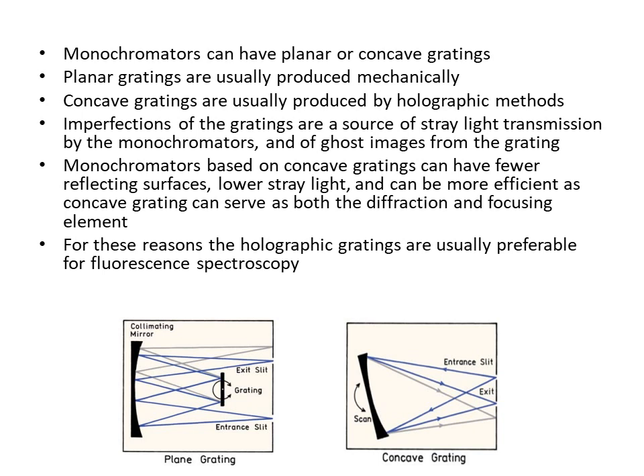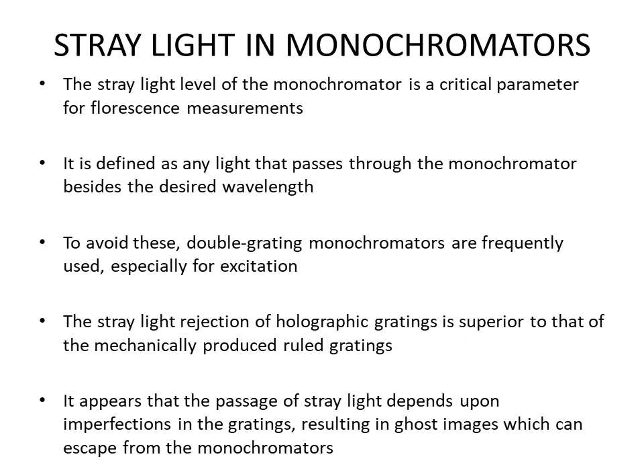Monochromators based on concave gratings have fewer reflecting surfaces, so there are lower chances of stray light and they can be more efficient. A concave grating serves as both a diffraction and focusing element. For these reasons, holographic gratings are usually preferable for fluorescence spectroscopy.